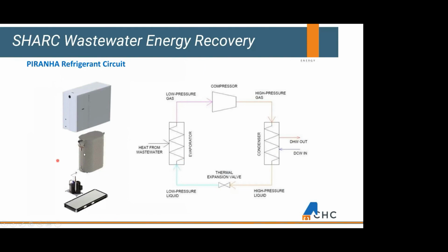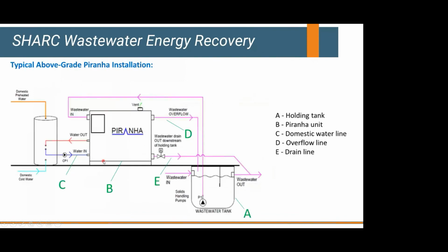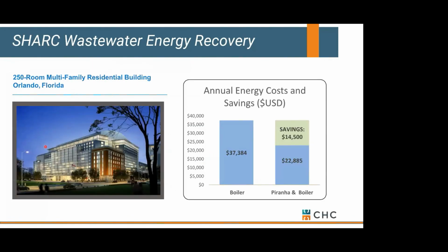And when all that sewage has given up its heat or temperature, they dump it back into the pit or the storage tank. Okay, and then there's going to be an overflow if this gets too full as it's coming in. So it's just one way to utilize sewage as domestic hot water. Pretty slick option. It just needs some design considerations. And there's certainly savings here. But it needs to be part of the early design process because you need a pretty good sized pit to store your sewage in order to transfer it back and generate heat from it throughout the night.